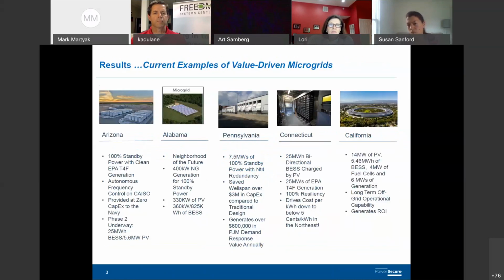In Yuma, Arizona, we provided a 25 megawatt microgrid at the Marine Corps Air Station that provides 100% clean EPA Tier 4 final generation resiliency to the base. It also provides autonomous frequency control on the California ISO, which probably has more duck curve events and intermittent renewable frequency issues than any other in our country. The value to the utility was avoiding T&D upgrades and other peak load management, and they were able to provide this to the Marine Corps at zero capital dollars—meaning taxpayers paid zero to make that important base 100% resilient.